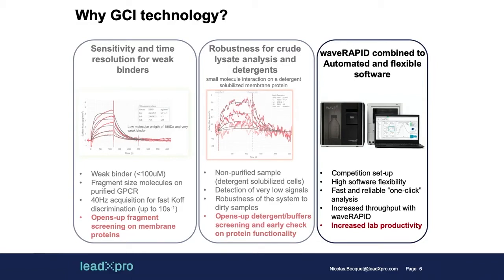In addition to that, we can acquire data at 40 hertz, which is very useful for weak binders with very fast off-rates, and it opens up fragment screening on membrane proteins. Sensitivity is really a crucial point for us because when we purify membrane protein, the percentage of activity is never super high, and we really need that sensitivity.